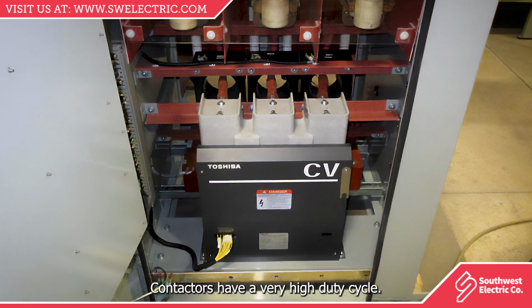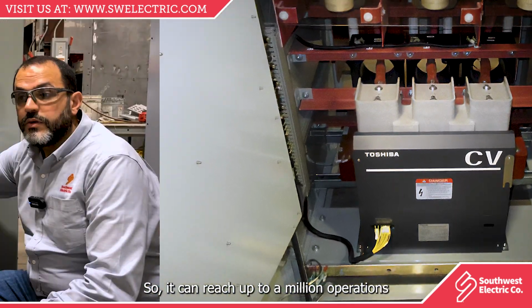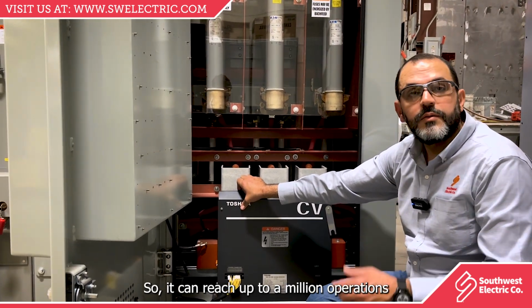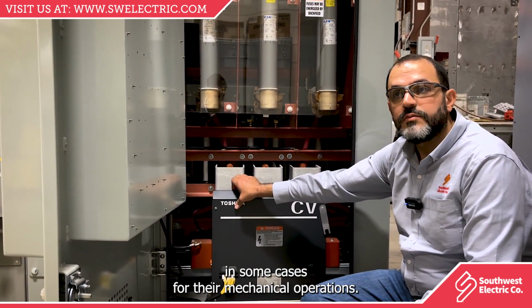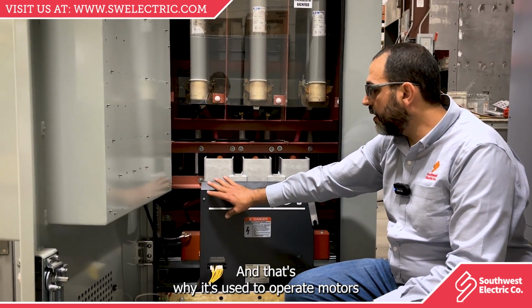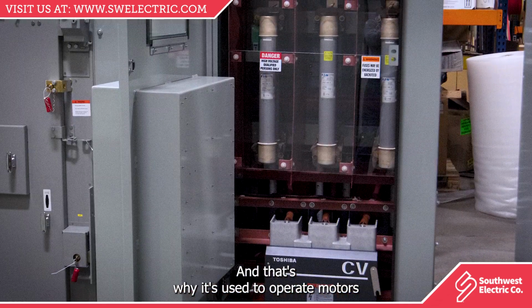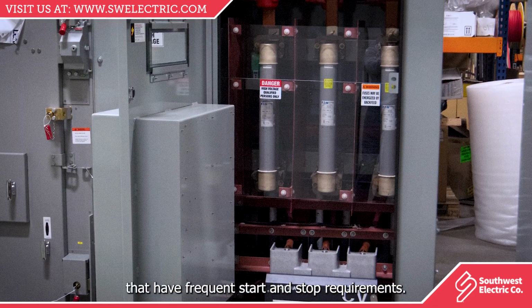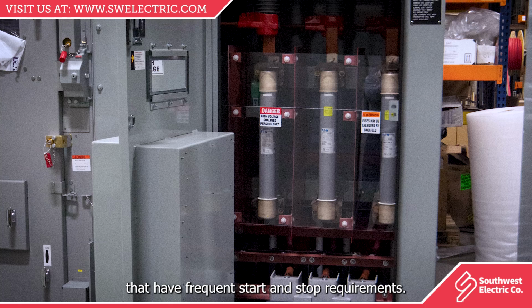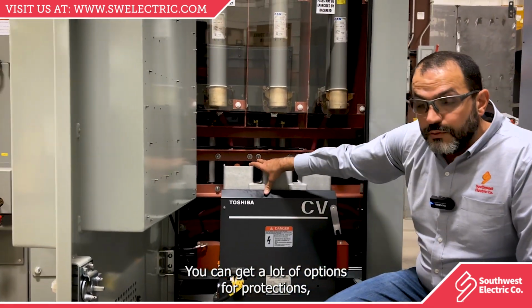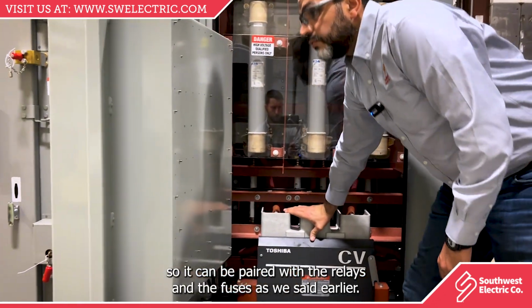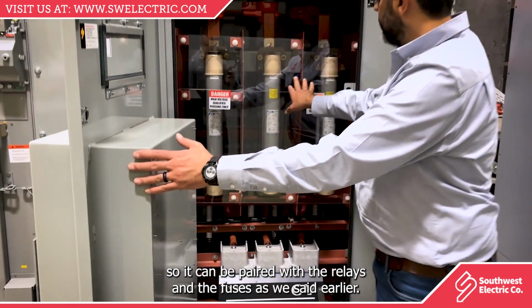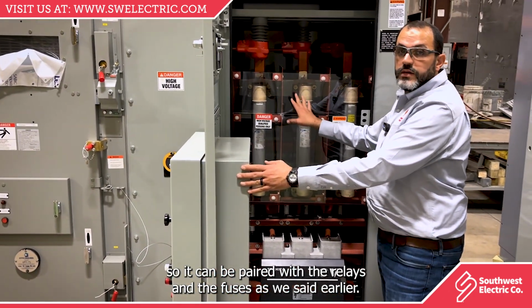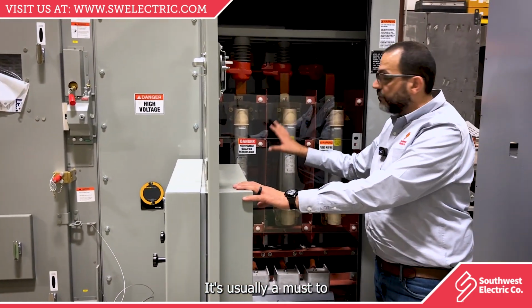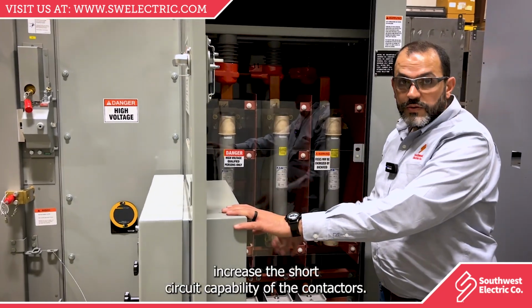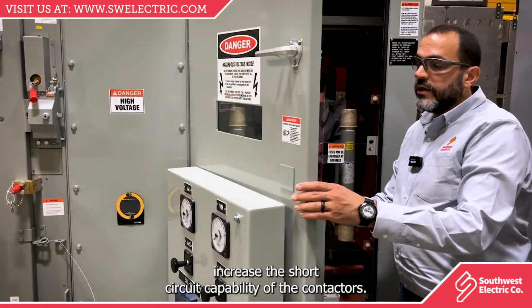Contactors have a very high duty cycle, so they can reach up to 1 million mechanical operations in some cases, which is why they're used to operate motors that have frequent start and stop requirements. You can get a lot of options for protection, paired with relays and fuses, since it's usually a must to increase the short circuit capability of those contactors.